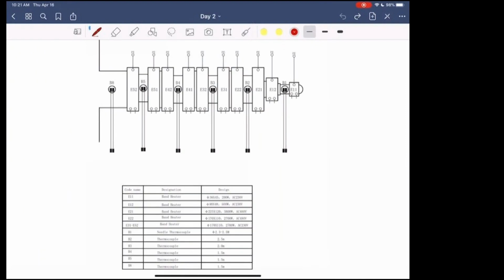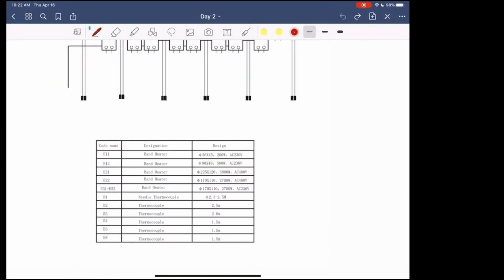This is your heater band circuit. The nice thing about the heater band circuit is they actually tell you what size the heater bands are. So, for example, E11 is a 36 by 45 millimeter heater band, 200 watts, and 230 volts AC. Down at the bottom, it tells you what the length of the thermocouple is. So B2 length of the thermocouple is 2.5 meters, and these are K thermocouples, not J.